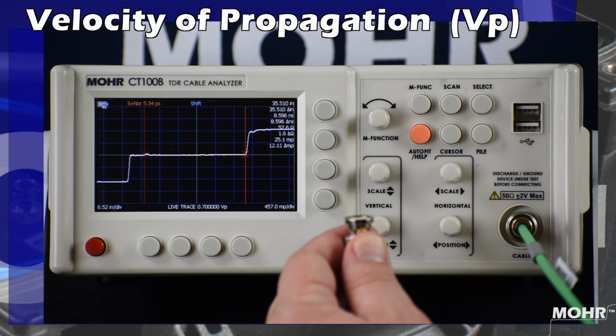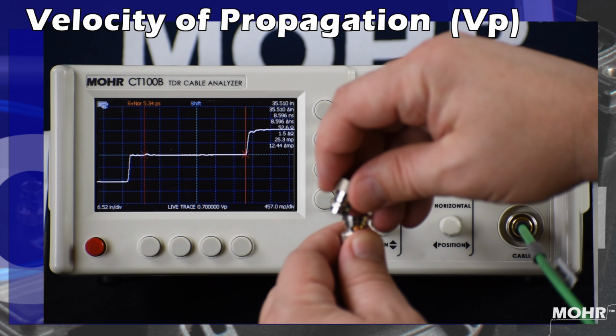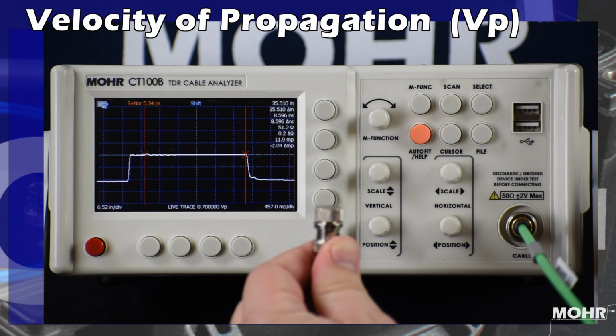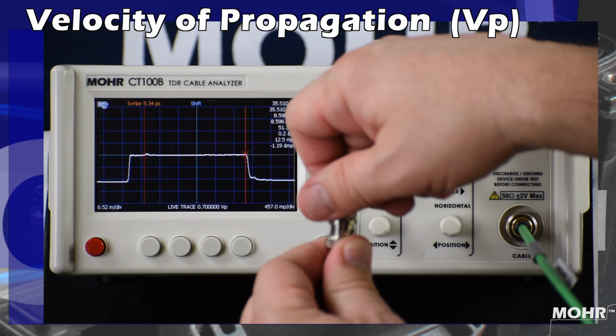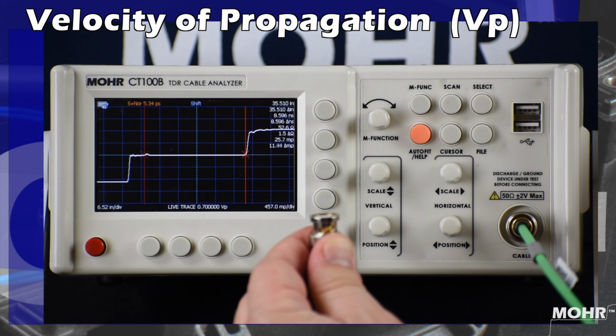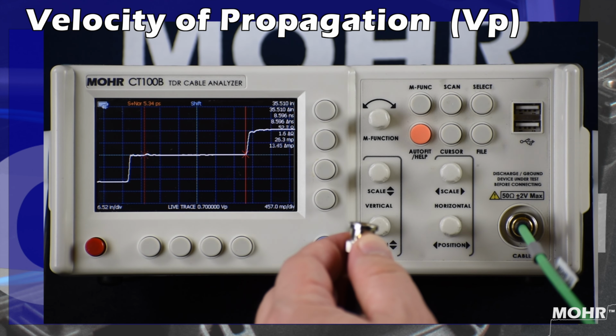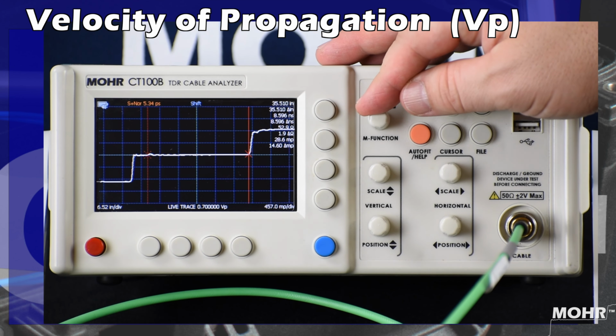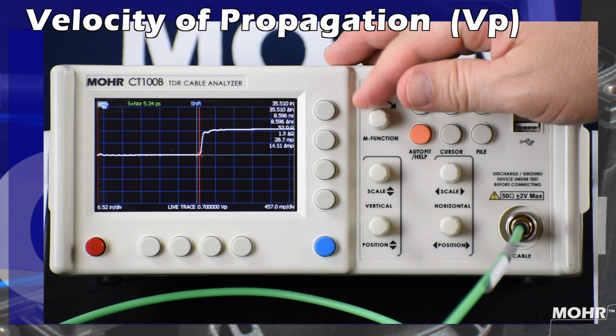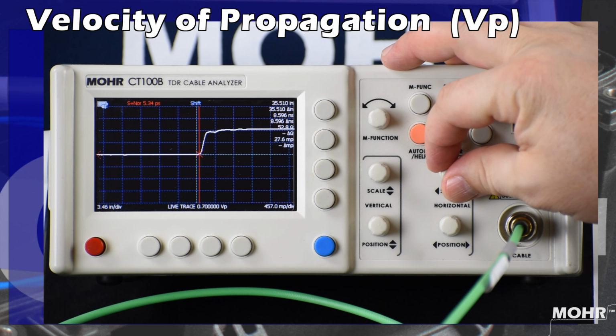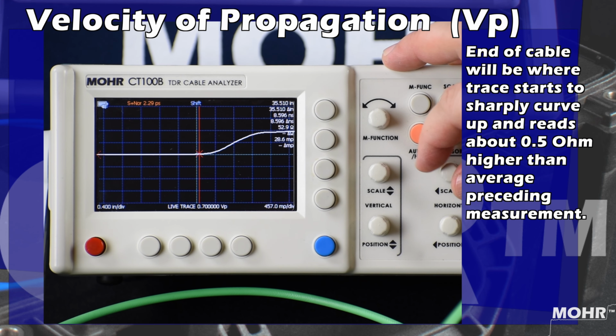Notice the appearance of the end of the cable when I connect a shorting cap to it and how it changes. This is how you know you're at the end of the cable and it's not damaged somewhere in the middle. Using the scale and position knobs, I'm going to zoom in and position the second cursor at the end of the cable.